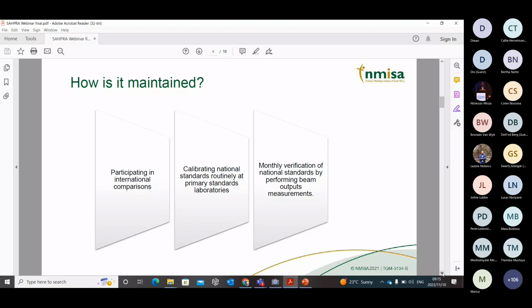So how do we maintain traceability? In terms of us as the laboratories or the National Metrology Institutes, we maintain traceability in three ways. We participate in international comparisons. We calibrate the national standards routinely at primary standards laboratories. And we also do monthly verifications of the national standards by performing beam output measurements for the standards that we have in the lab.